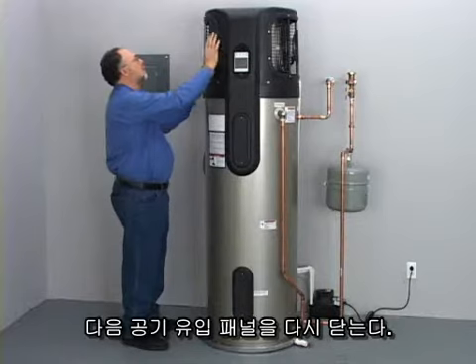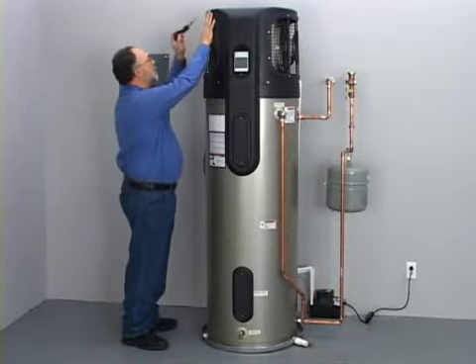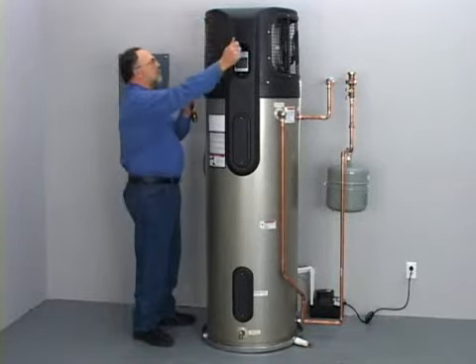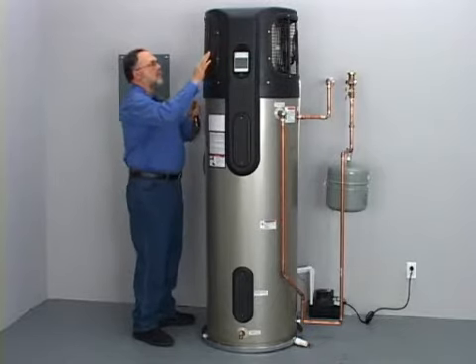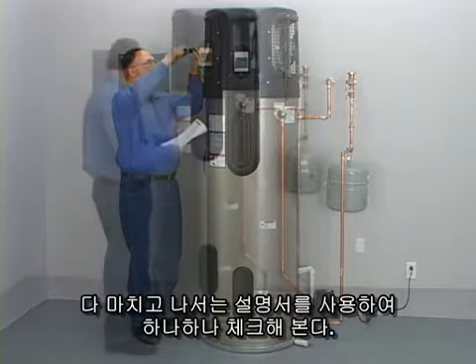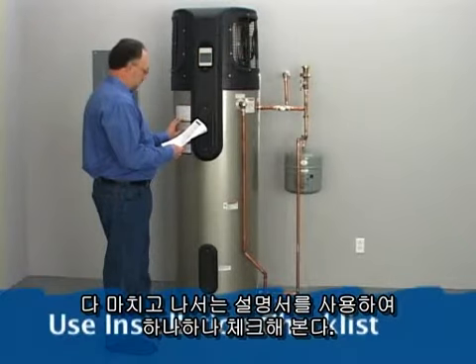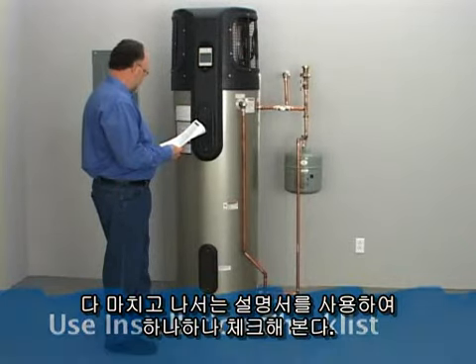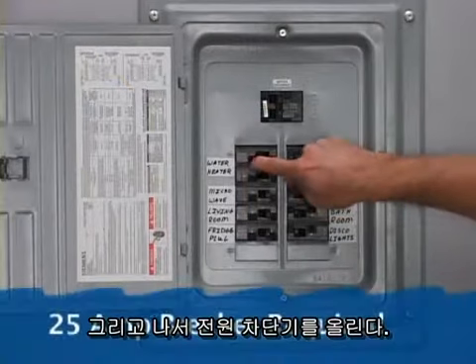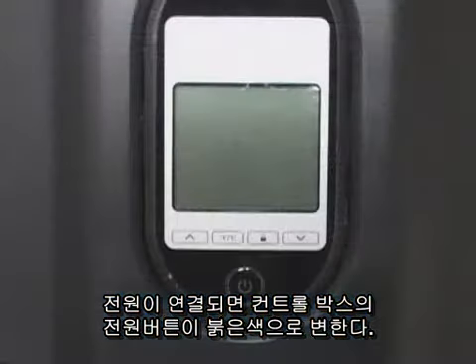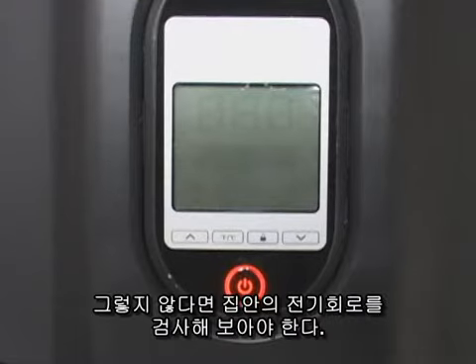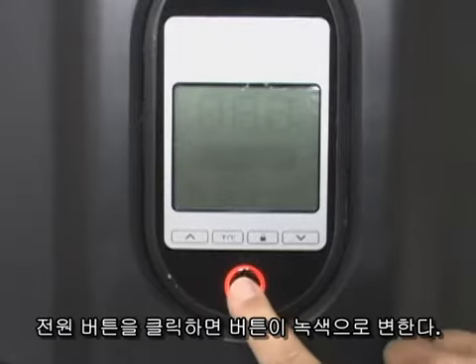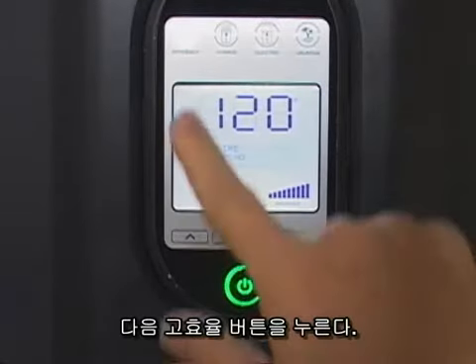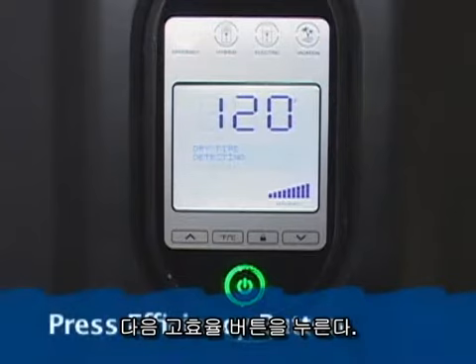Reinstall the louvered panel. Also reinstall the air filter. Make sure every item on the installation checklist has been followed. Turn the circuit breaker back on. The button on the front of the water heater should display a red light. If not, check your home's electrical wiring. Press the power button, which will now turn green. Next, press the efficiency button.